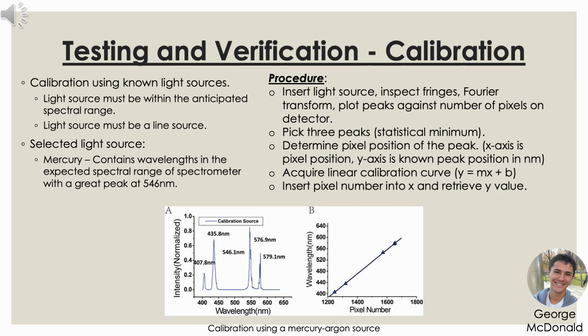So this is testing and verification by calibration. Basically, all you do is select a light source that has distinct peaks. It's a line light source, but it has distinct peaks at specific wavelength locations. In our case, we chose mercury, and it has a high intensity peak at 546 nanometers, which will be helpful in selecting specific peaks for calibrating.